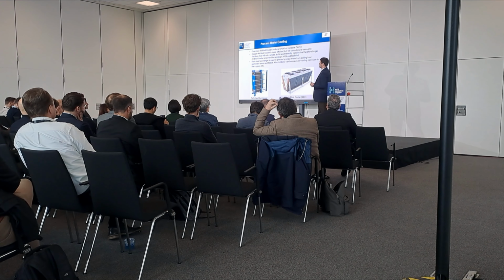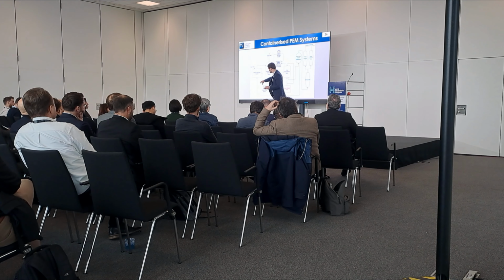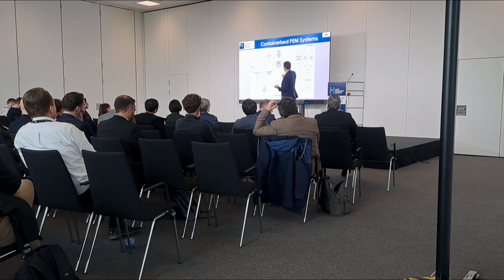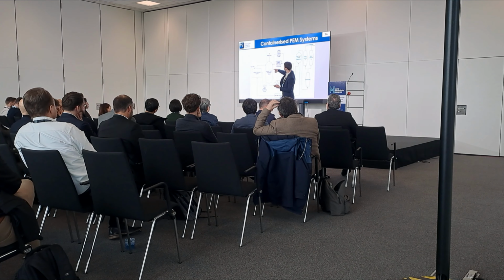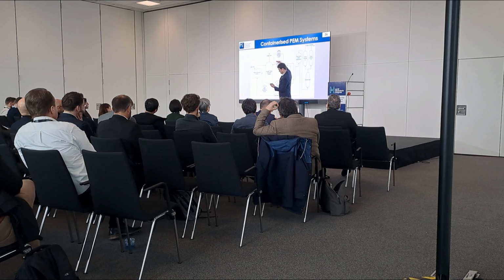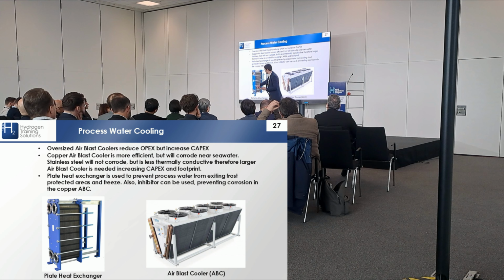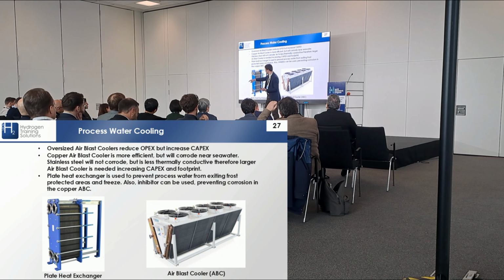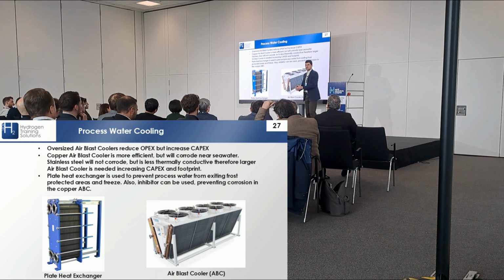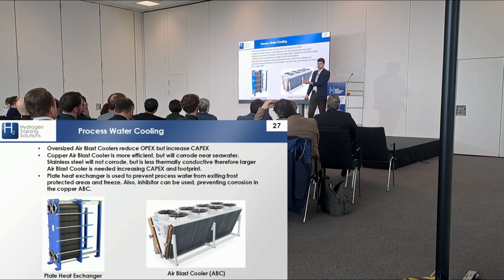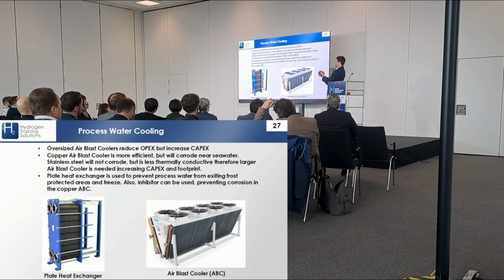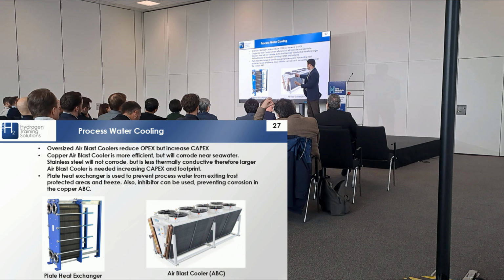So we've got the plate heat exchanger. Of course, the process water that comes out of the electrolyzer stack will go into the plate heat exchanger, and in the plate heat exchanger there's going to be a stream in which is processed water, a stream out which is also processed water, but then we'll have a cooling medium going in and a cooling medium coming out. And one of the reasons that we need the plate heat exchangers and we can't just put the water straight into the air blast cooler is that it's going to freeze, because this must, of course, be outside.